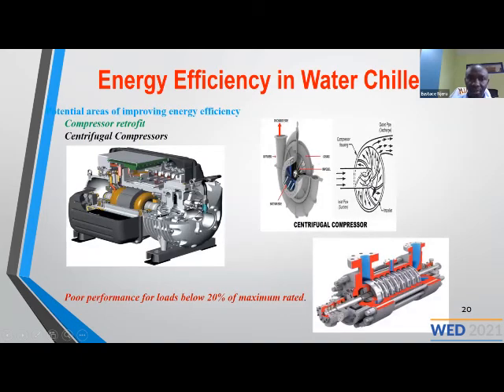These are the centrifugal compressors. This one is a two-stage. You can see it has two turbines, two impellers. As I've said, it operates more like a centrifugal pump or fan, but it is capable of operating at higher pressure. So if you want higher pressures, you can use a two-stage or a multi-stage. These are two-stage centrifugal. The good thing with centrifugal compressors is they handle very big volumes of refrigerant compared to the screw and the reciprocating.